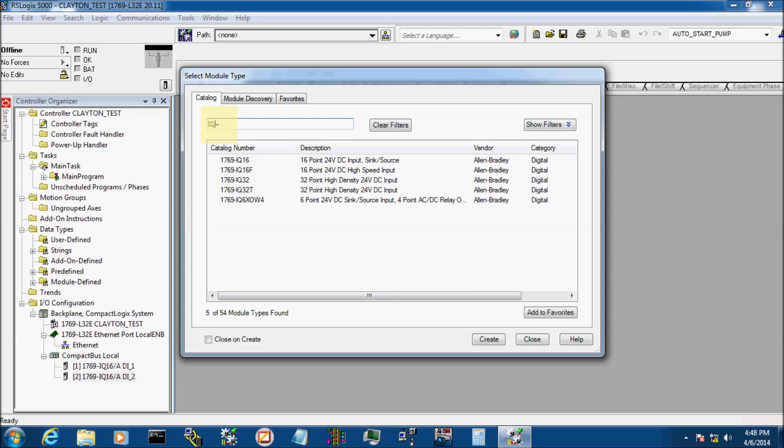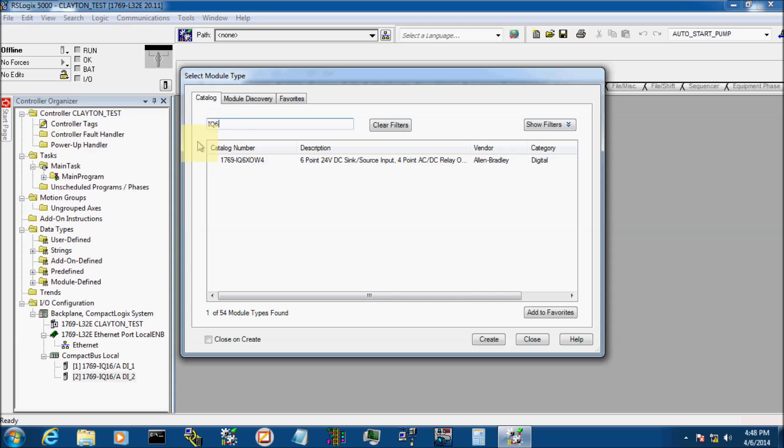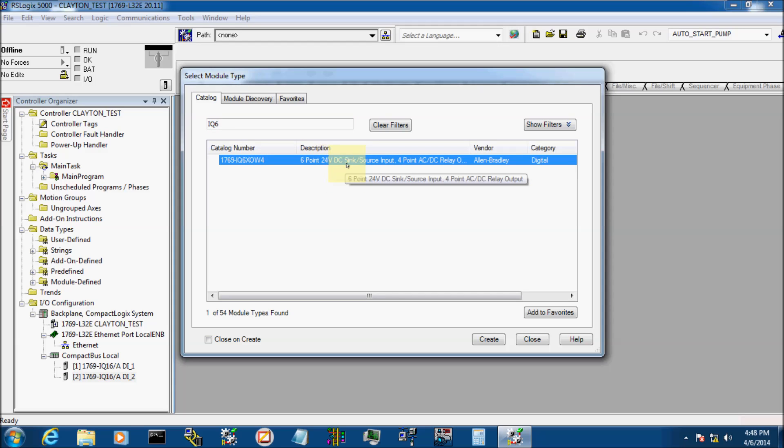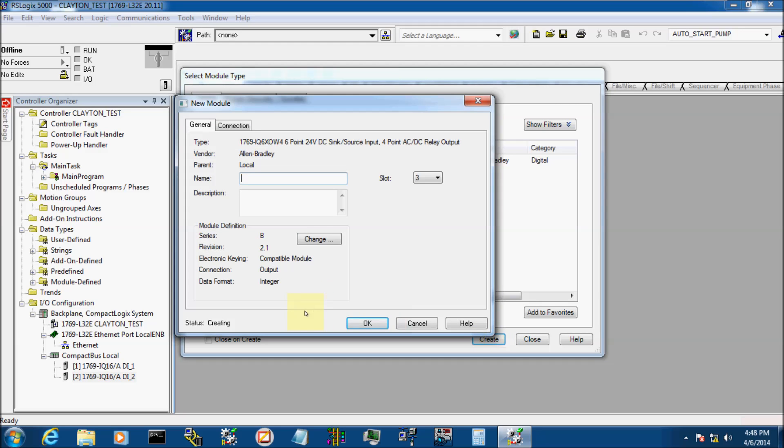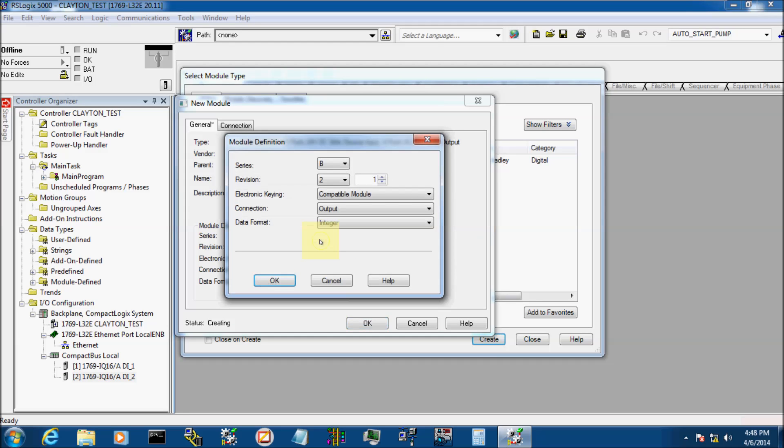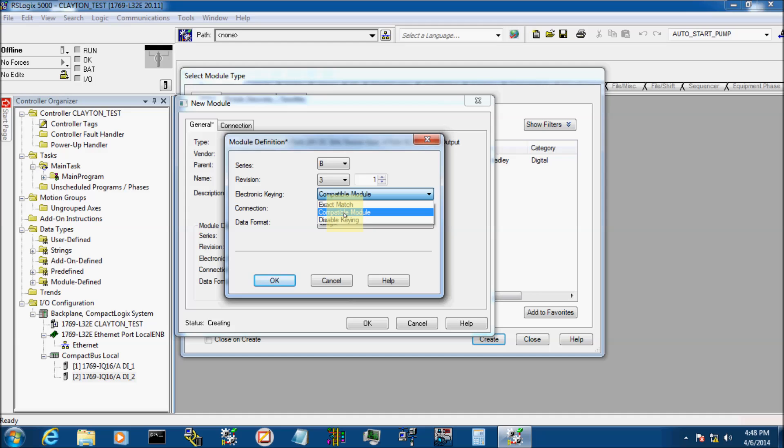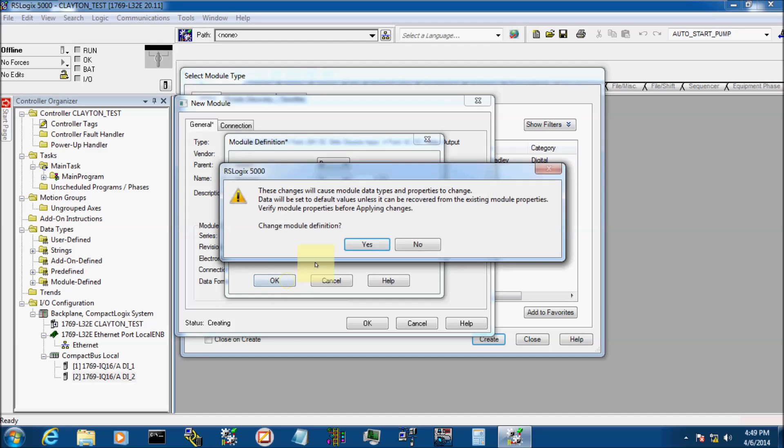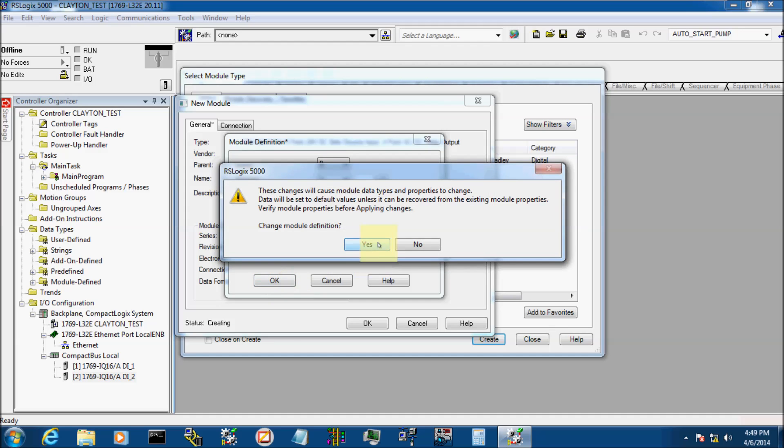My third card is an IQ6 XOW4. It's actually a combo card. It's 6 DI, 4 DO. Go ahead and create that. We're going to call this one Combo. So my combo card is a Series B Revision 3.1. You always want to use Compatible Module. That way, if you have to change this card out at some point, you don't have to have a card with the same firmware revision. You can have any firmware revision. So we're going to say OK.